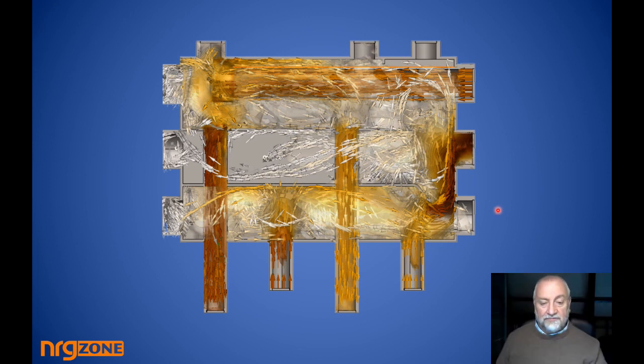Let's put some figures on this. Say the heat pump had been taking back 40 degrees and heating it to 45 degrees, so our 45 degrees would have been coming here. And now let's say the gas boiler goes from 45 to say 65, with a 20 degree drop. So the heat is taken out from the zones and then is heated to the delta T that you've decided. It's put across the top chamber, and it arrives at this point. It's taken down at the same flow rate that the zone requires, because the zone pump determines what's going to go through that connection. Same with this zone's pump out here, and the cold water is brought back up in, and you can see here that it's actually drawn across and off out and into the gas boiler.